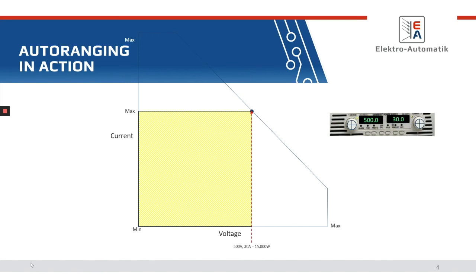So here, for the theory of operation, we have a 15 kilowatt power supply that's capable of 500 volts and 30 amps. Part of the challenge that customers have is, how often do you actually operate at 500 volts? Maybe it's 450 volts, maybe you're down to 300 volts, 150 volts. As you program down in voltage, the available current from that power supply stays the same, meaning the power supply will never provide more than 30 amps of current, 500 volts, 15 kilowatts. So as you're programming down in voltage, say at 250 volts, you're still getting that 30 amps, you're only at 7,500 watts. So here you purchased a power supply that's capable of 15 kilowatts, but at half the voltage, you're only getting half the power.